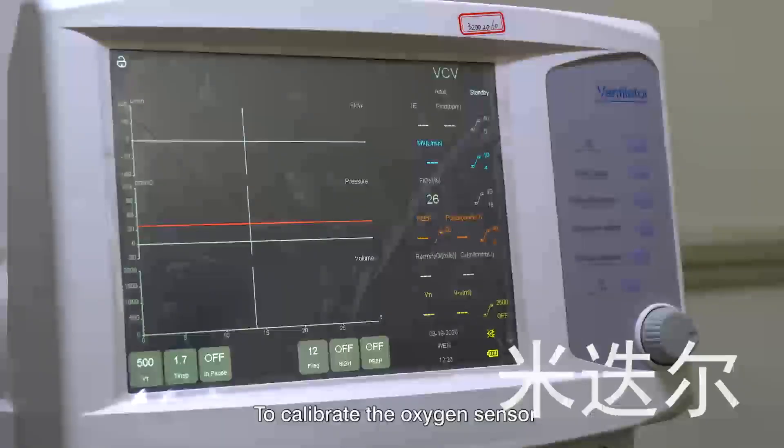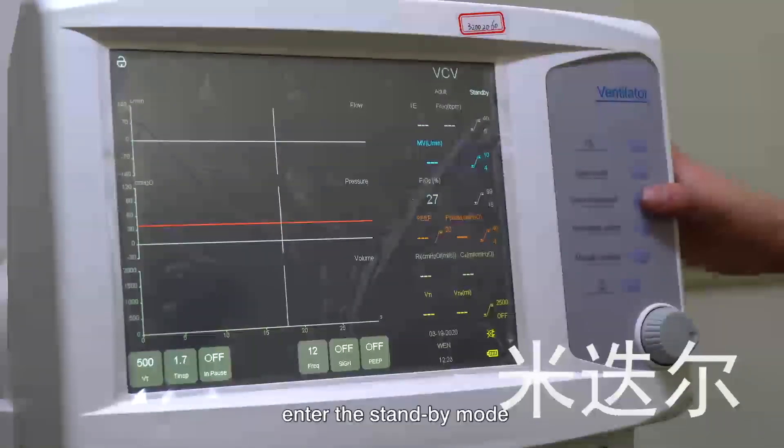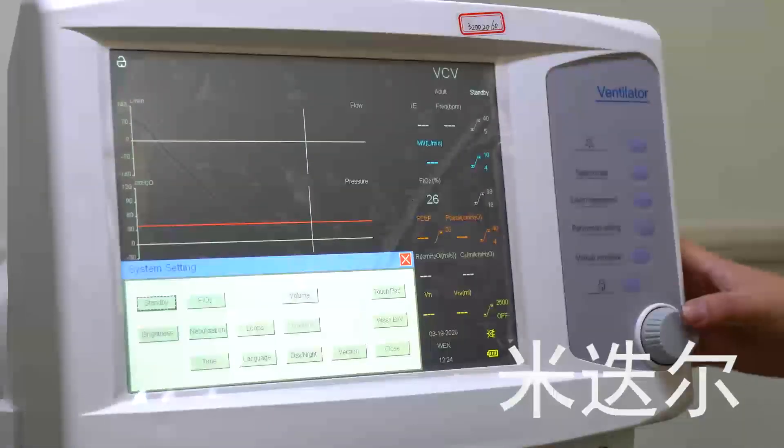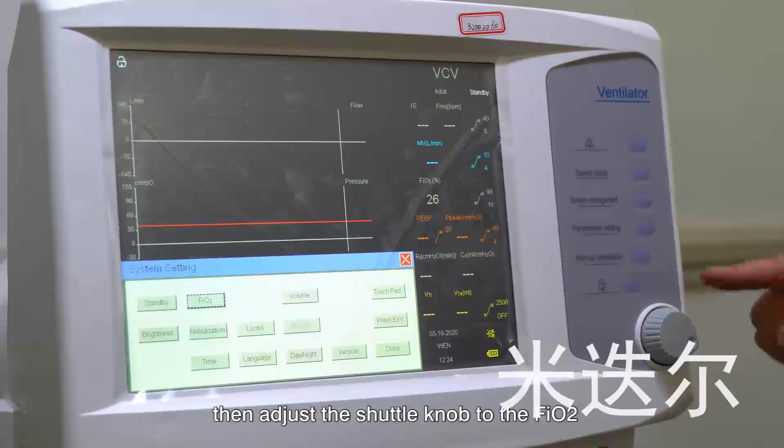To calibrate the oxygen sensor, enter the standby mode, then press the setting management. Then adjust the shuttle knob to the FiO2, press and the machine will automatically recalibrate the sensor.